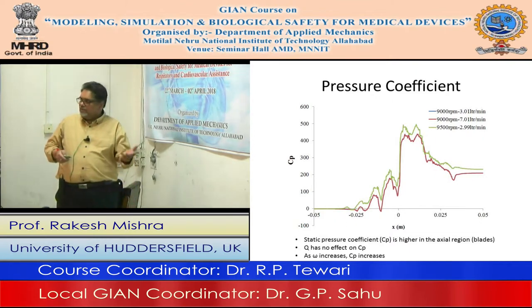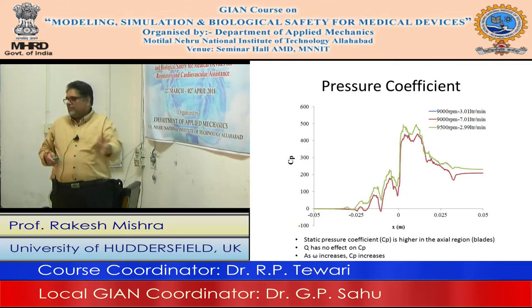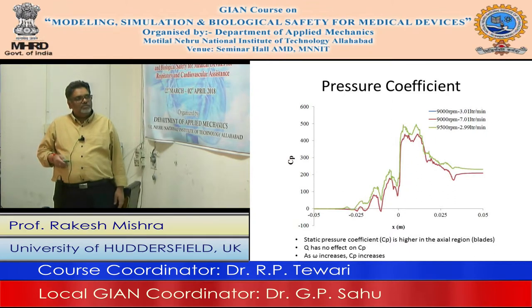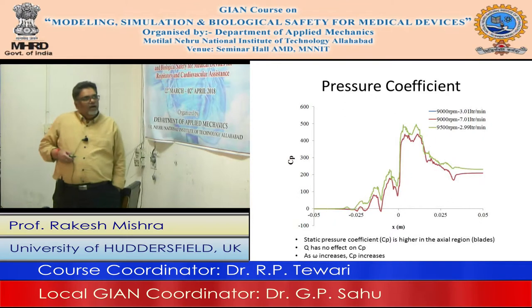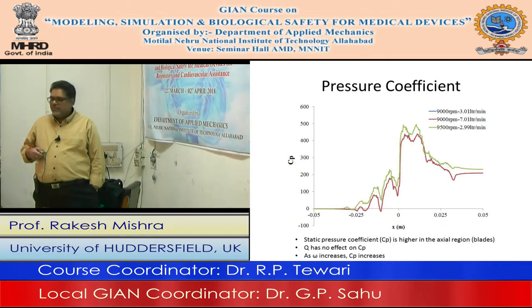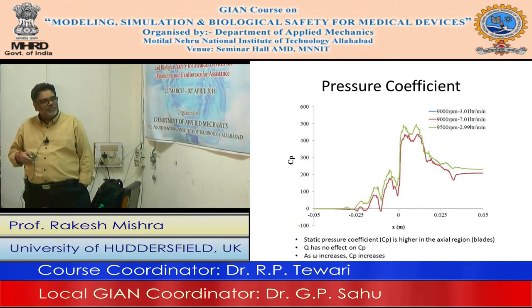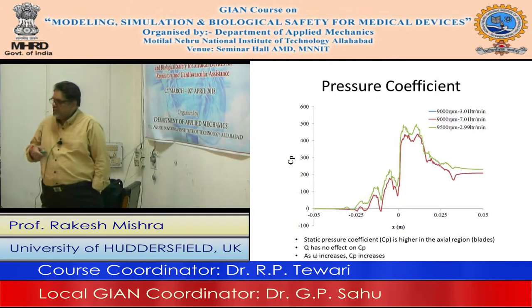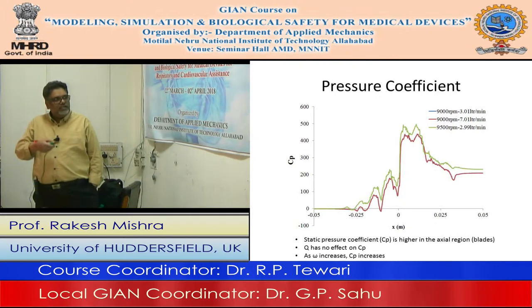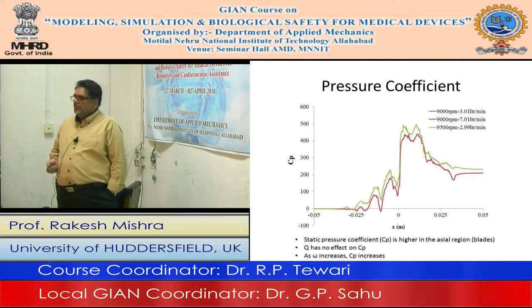You can see which part is contributing more to the pressure rise and why. That can affect your design — you can modify the design so that the first part also starts getting the same type of pressure rise. Then calculate the change in pressure contributions as the flow rate and speed change. Carry out parametric investigations: change the impeller angle, change the impeller dimensions, and calculate all these things again. This is a good tutorial exercise for in-depth analysis.